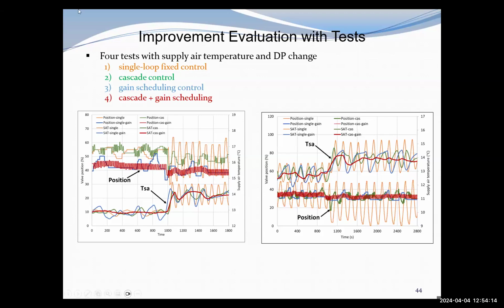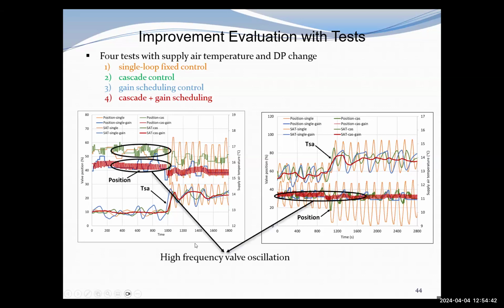Here, if we focus on the supply air temperature response, we can see the red curve is very good. It's very smooth and fast. And the orange curve is oscillating, right? But if we look at the control valve, the valve position response, we can notice that the red curve has very high frequency valve oscillations, right? We don't want that to happen.